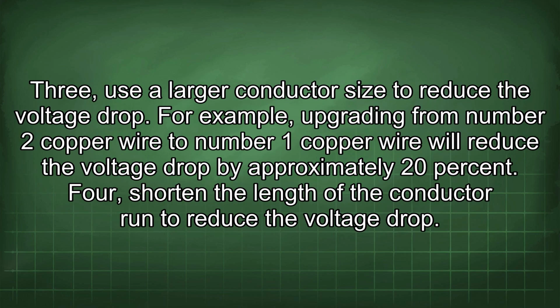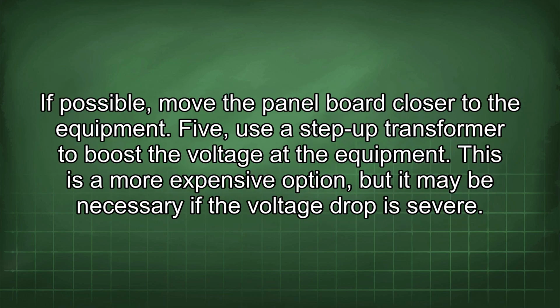3. Use a larger conductor size to reduce the voltage drop. For example, upgrading from number 2 copper wire to number 1 copper wire will reduce the voltage drop by approximately 20%. 4. Shorten the length of the conductor run to reduce the voltage drop. If possible, move the panel board closer to the equipment. 5. Use a step-up transformer to boost the voltage at the equipment. This is a more expensive option, but it may be necessary if the voltage drop is severe.